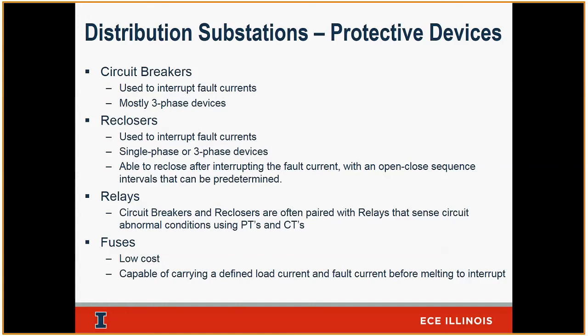Sometimes you see blinks in your lights. That's what's happening. A recloser just saw a fault. It opened real quick and closed to see what's going on. So 5 seconds, then 15 seconds will be the next interval. The second time it will wait 15 seconds, again, to see if the fault cleared or not, and we'll try again. The fault is still there. We'll try one last time 30 seconds later, and the fault is still there. We're going to open permanently until we figure out where the fault is and what's going on, right?